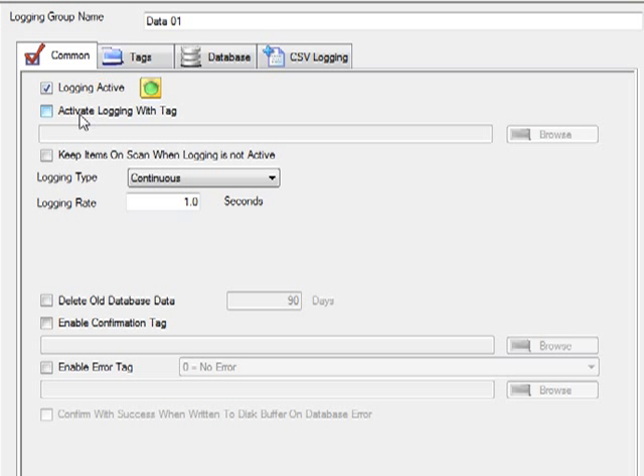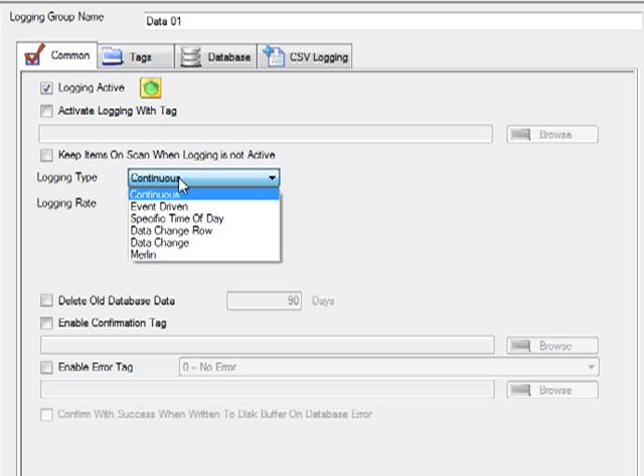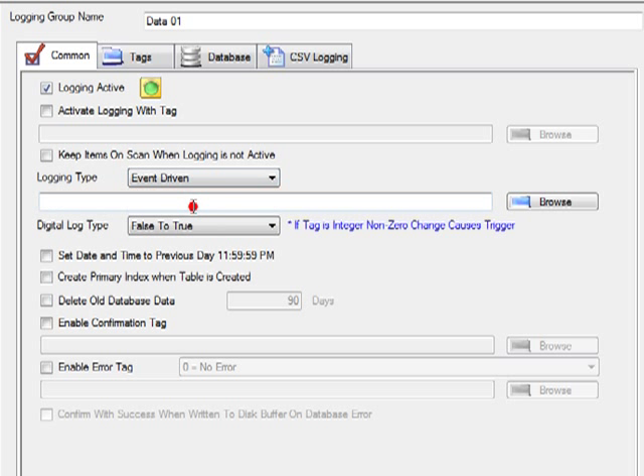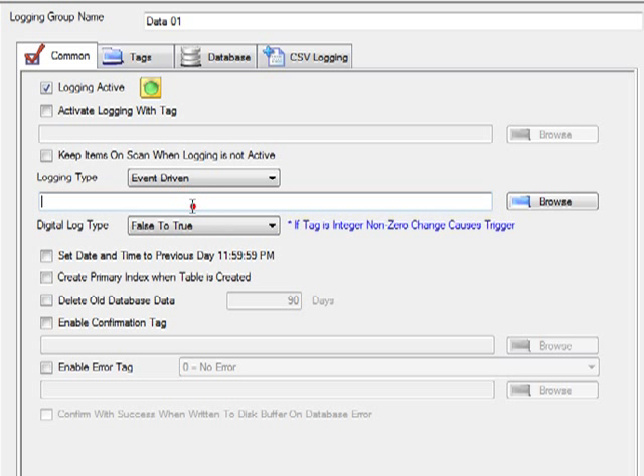Notice that you can control the logging active from another OPC Systems.NET tag or direct OPC item. We would then specify the logging type. The logging types that we can do are continuous at a specific rate, or event driven. If we do event driven, we define a trigger tag that would be either an integer tag changing or a boolean tag that transitions. When that trigger occurs, it will log all of the values that we're about to define under the Tags tab.